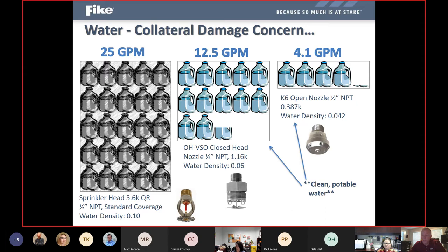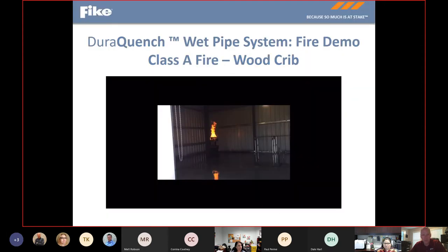Traditional sprinkler heads might be designed or expected to put out about 25 gallons per minute, whereas our water mist systems are going to be at least half, and in some cases much less than that, of clean water because we're hooking into the domestic or potable water supply at the site. So the same water you would drink or use to clean up the facility is the water we're going to discharge to extinguish a fire.